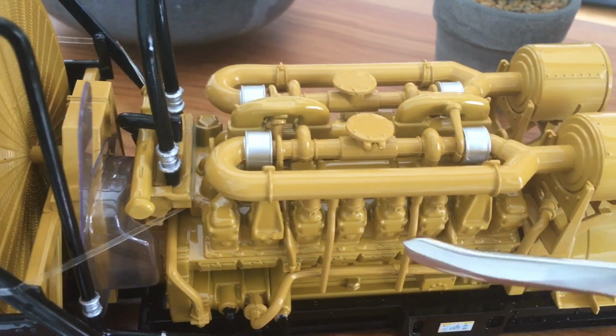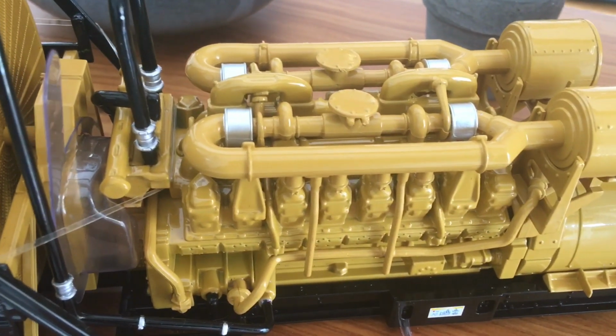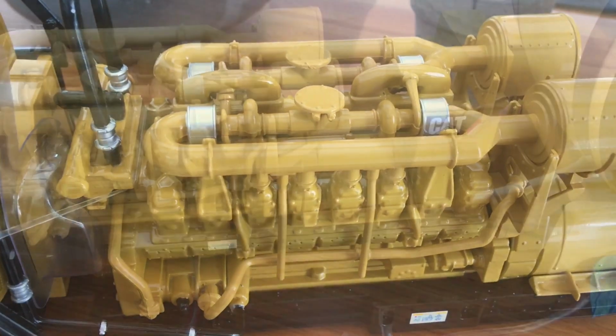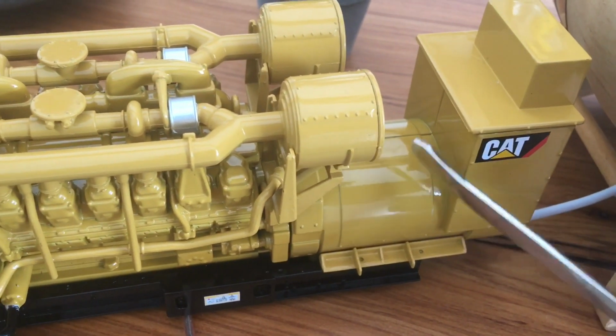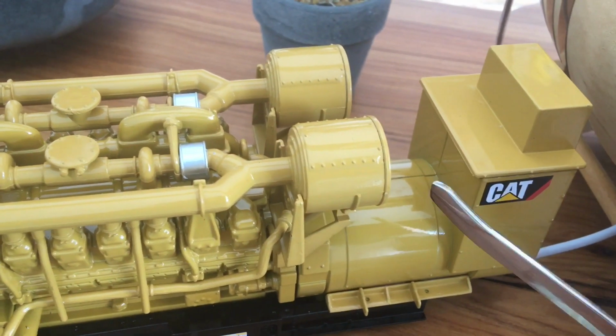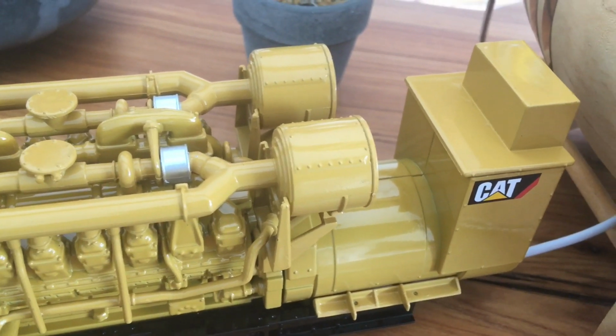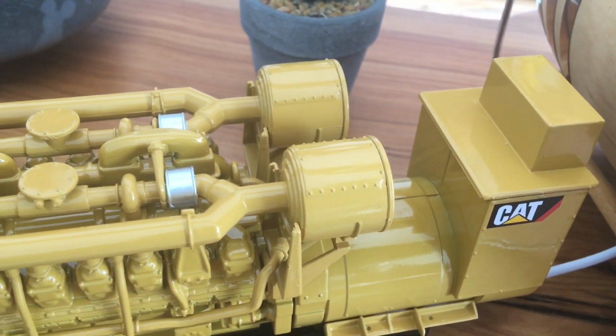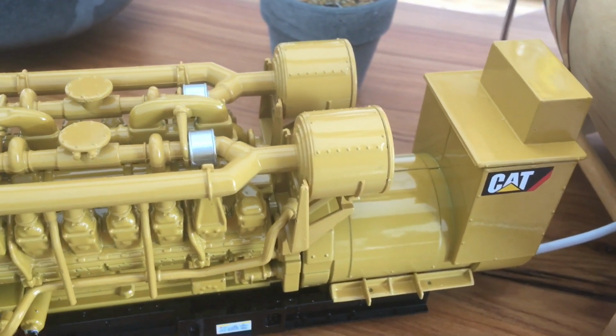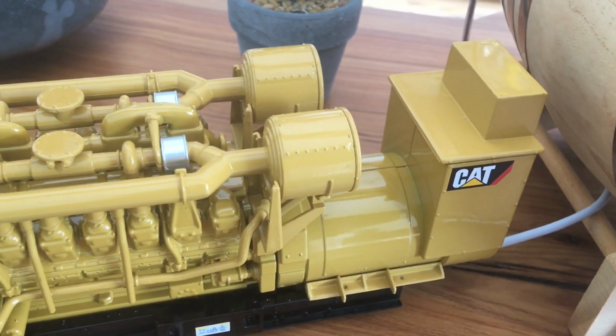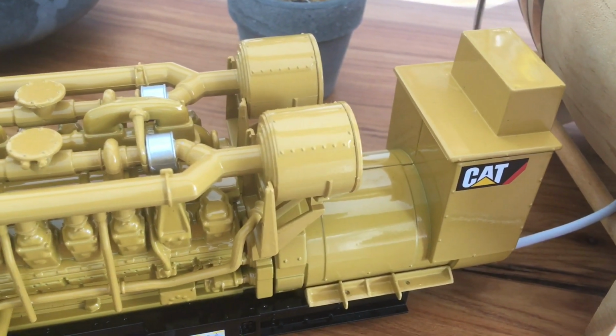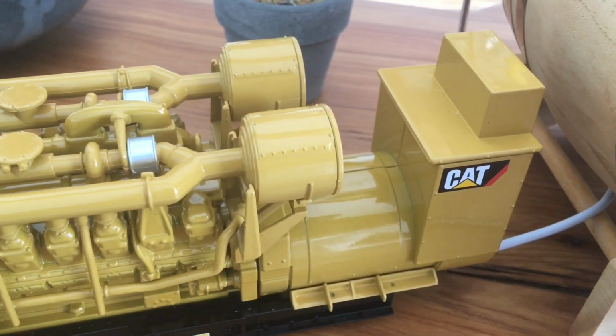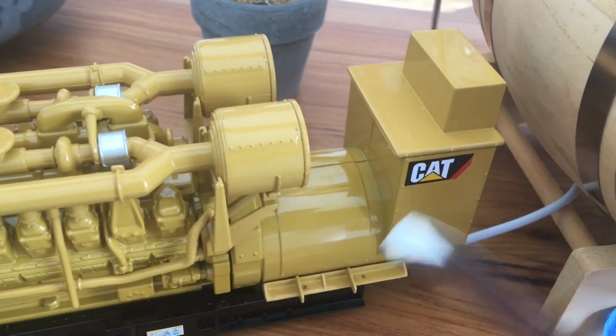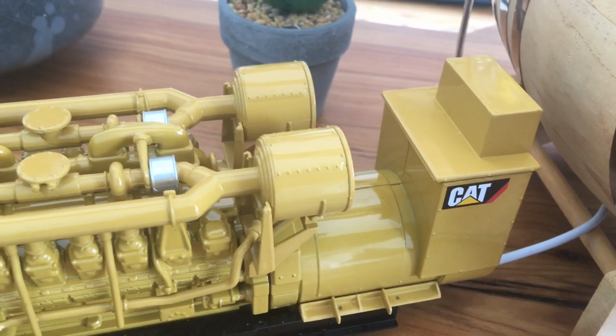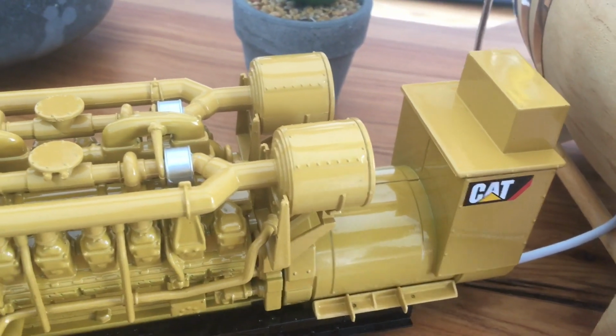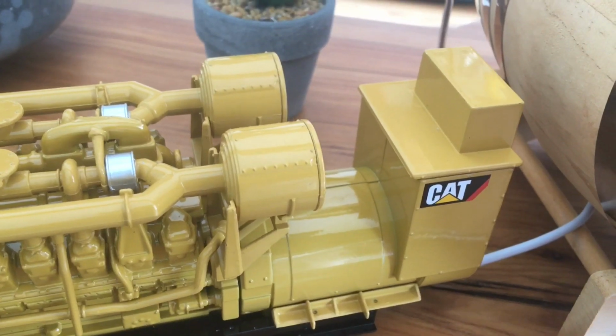So be very careful with a Chinese engine, you better load it properly with the proper power. You need to power up the engine, use a load bank, and try to go up to 95% load. Stagger it: start from 15% for say 2 hours, then 20%, 25, 40, 50, 60, 70. You need to power it for about 24 hours, and the maximum you achieve, 95%, would be the desirable load.